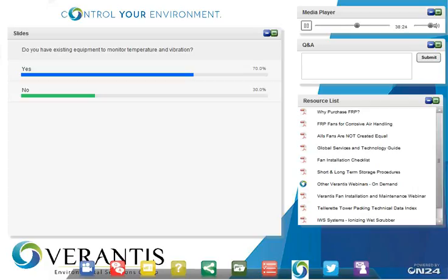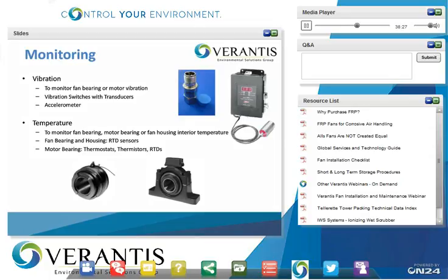And we'll turn this over to Sherry Lew at this time. Vibration and temperature. Usually, high vibration level is a really common cause for fan failure, because as the fan runs over time, impeller vibration level will get worse, and it is usually caused by buildup and wear. It is critical for people to monitor vibration level and make necessary actions to avoid any severe future failure. For vibration level setup, it usually has two levels, one for alarm and one for shutdown.